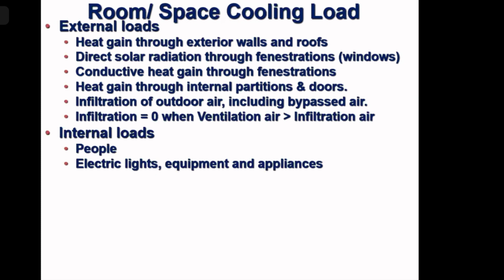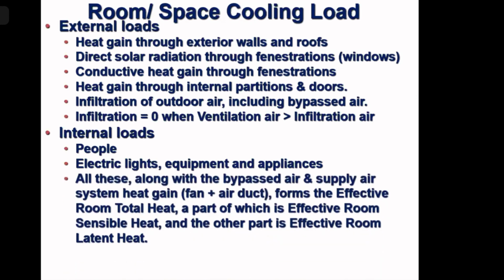Then internal loads. Internal loads are people, electric light, equipment and appliances. Then, next. All these along with the bypass air, and supply air system heat gain, fan, air duct, form the effective room total heat we discussed. A part of which is effective room sensible heat and the other part is effective room latent heat. Next. Effective room sensible heat is used to determine the supply air fan capacity, the air handling unit fan capacity.